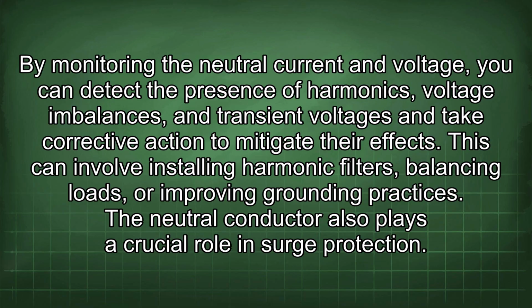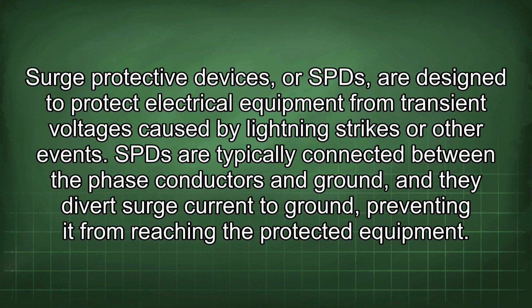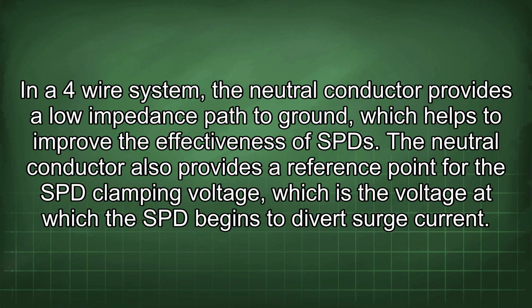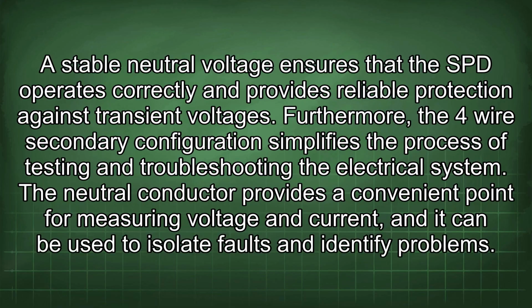The neutral conductor also plays a crucial role in surge protection. Surge protective devices, or SPDs, are designed to protect electrical equipment from transient voltages caused by lightning strikes or other events. SPDs are typically connected between the phase conductors and ground, and they divert surge current to ground, preventing it from reaching the protected equipment. In a 4-wire system, the neutral conductor provides a low impedance path to ground, which helps to improve the effectiveness of SPDs. The neutral conductor also provides the reference point for the SPD clamping voltage, which is the voltage at which the SPD begins to divert surge current. A stable neutral voltage ensures that the SPD operates correctly and provides reliable protection against transient voltages.